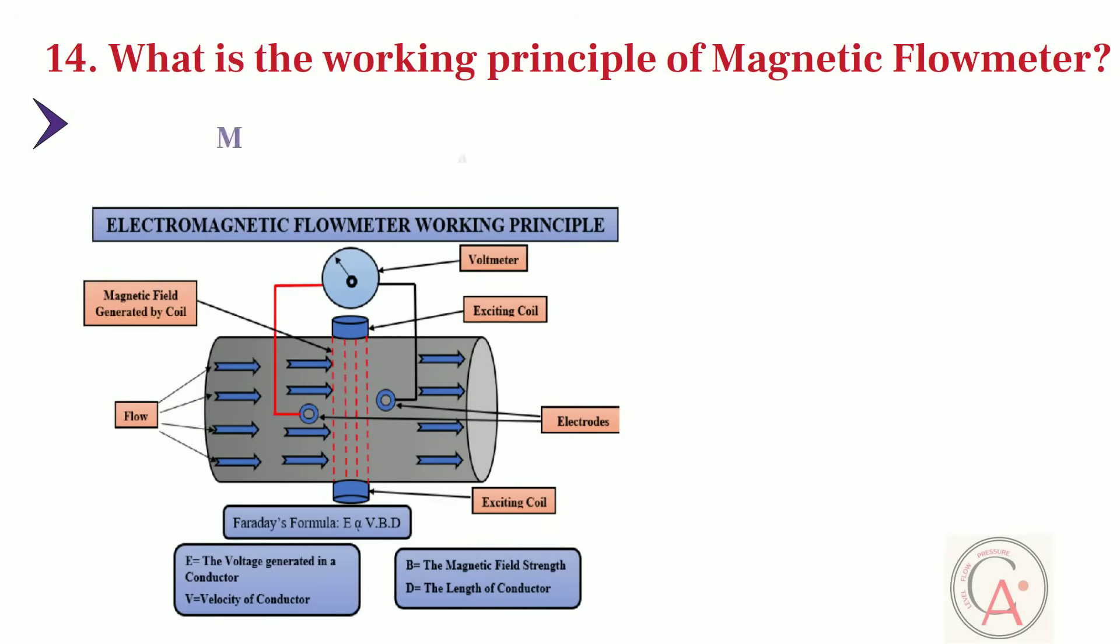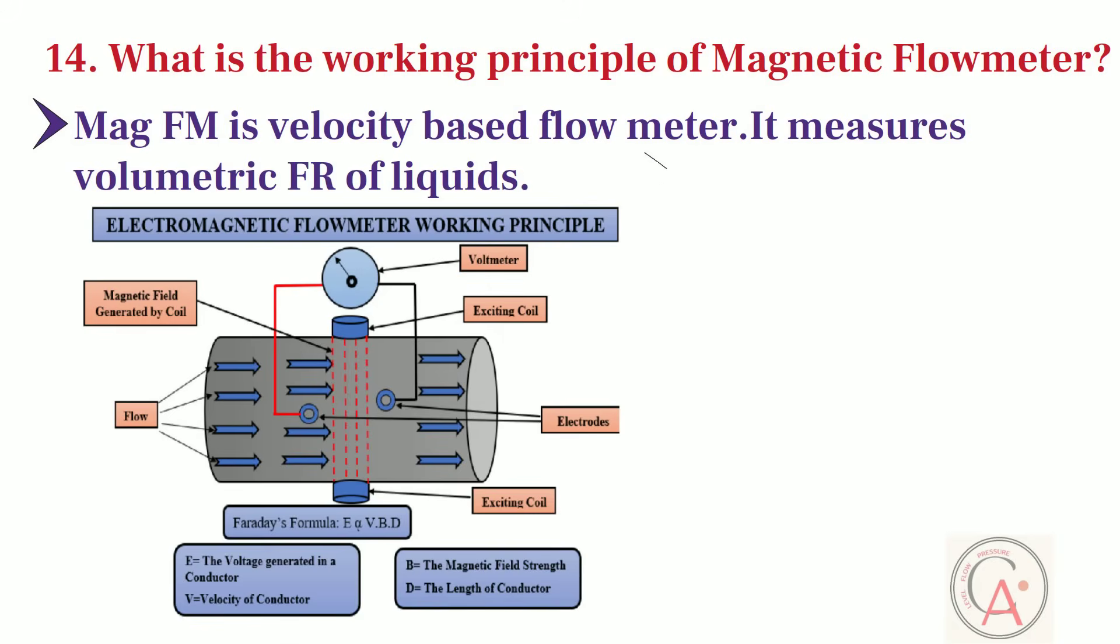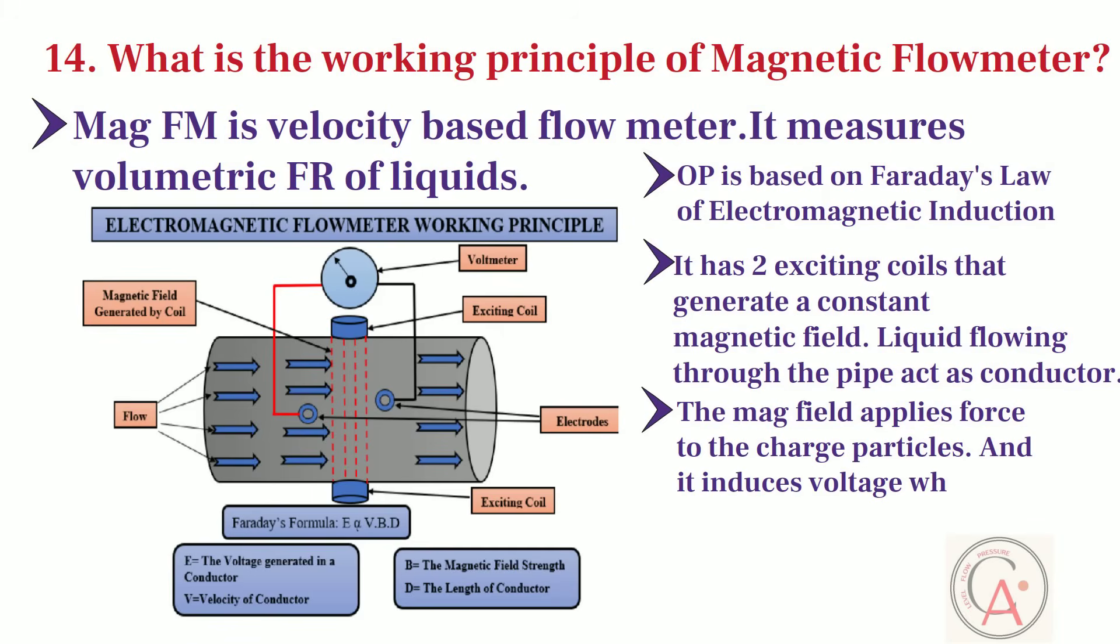Next question is, what is the working principle of magnetic flowmeter? Electromagnetic flowmeter is velocity-based flow meter, and it measures volumetric flow rate of liquids. Magnetic flowmeter's operating principle is based on Faraday's law of electromagnetic induction. Mag flowmeter has two exciting coils that generate a constant magnetic field, and liquid flowing through the pipe act as conductor. When conductive liquid such as water flows through the pipe or tube, the magnetic field applies force to the charge particles, which induces voltage which is detected by two sensing electrodes mounted in mag flow meter body.